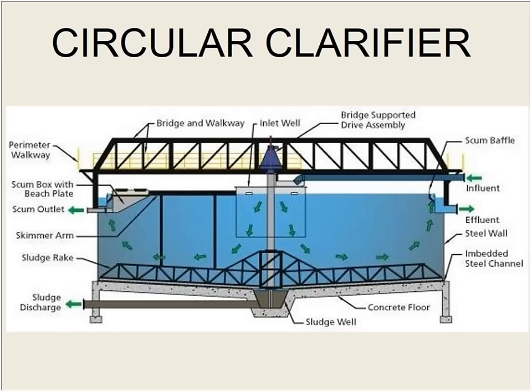And what we've got is another baffle. It's a big circular wall. It goes about 3 feet below the surface. So the water comes in, can't go straight over to the effluent. It has to hit that wall, come down, and slowly work its way up again. 1 foot per minute. Solids drop to the bottom, floatables go to the surface, hopefully. All is good. We've got a rake mechanism that's going to plow this into a well, and again, that comes off to be pumped out later.